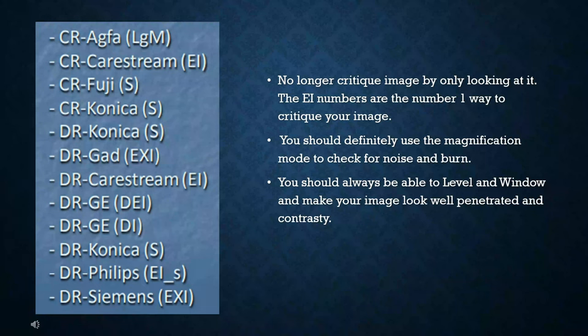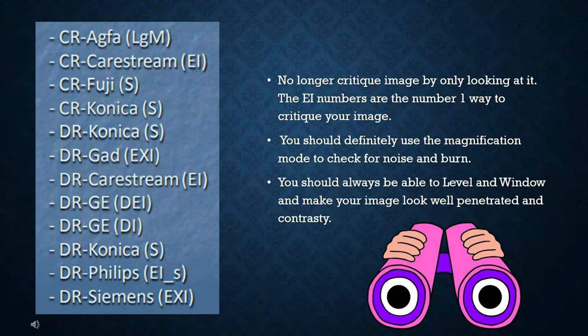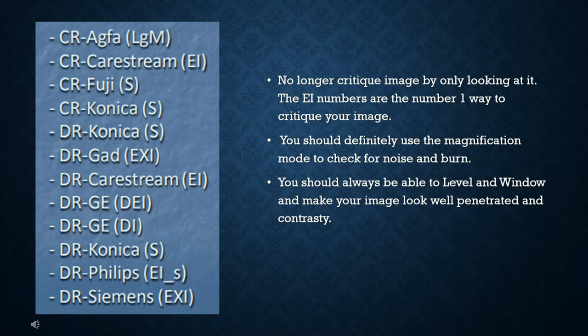This makes a big difference with your technique because you can no longer look at an image the way you did in the film days and know it's acceptable. You should look at the EI index numbers for the type of equipment you use. Use magnification to zoom in and check for any noise or burn. You should always be able to level and window to make your image look well-penetrated and contrasty.